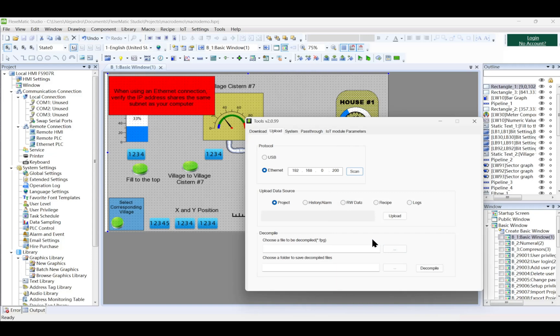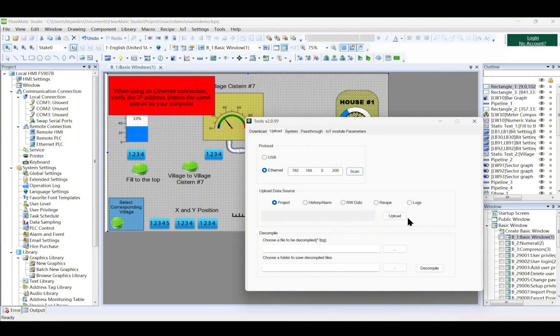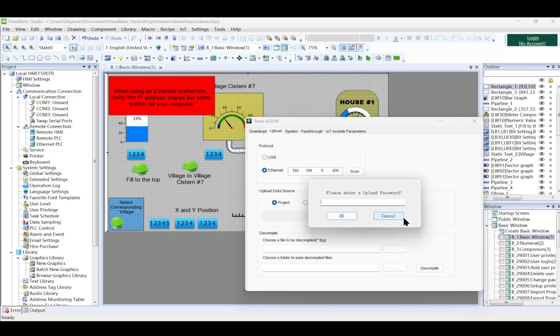Initiate the upload. From the menu bar, select Tools, Upload. In the pop-up dialog box, choose the communication method. If using Ethernet, set the IP address or IP segment of the HMI and click Scan to locate the device. Select Data to Upload.